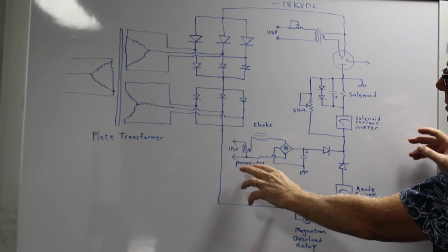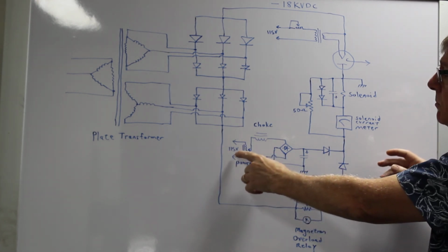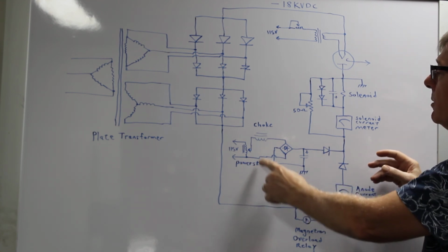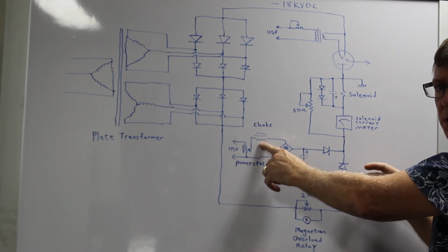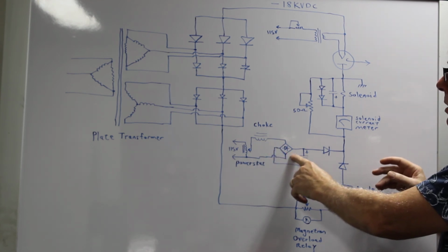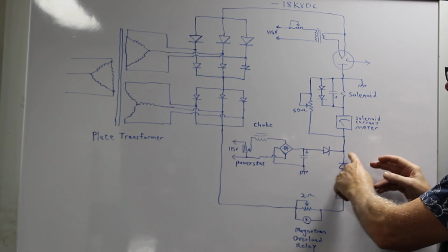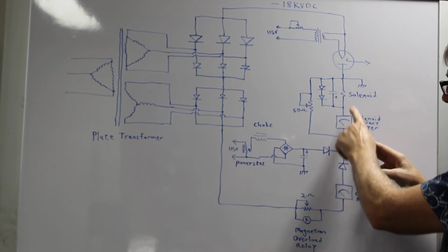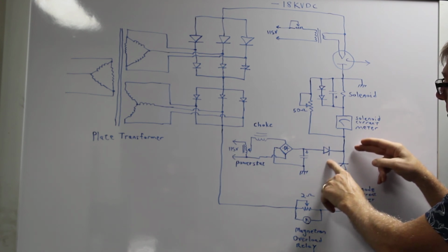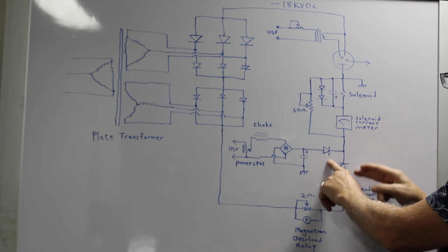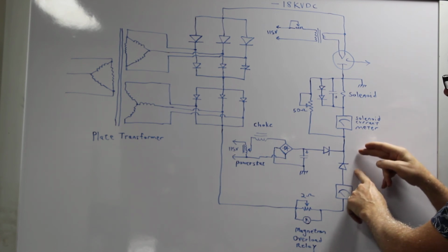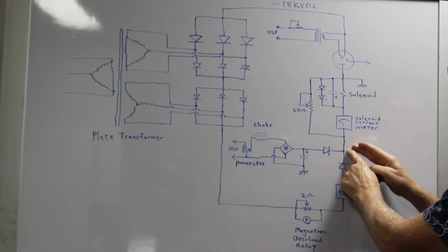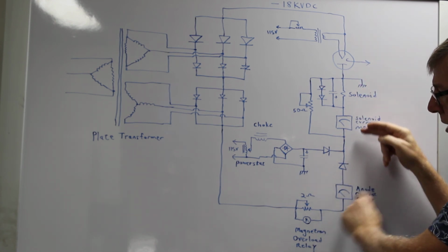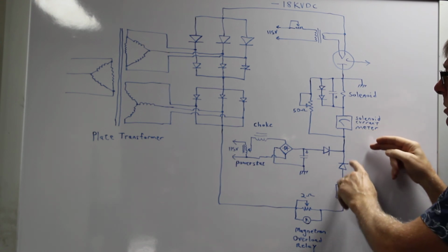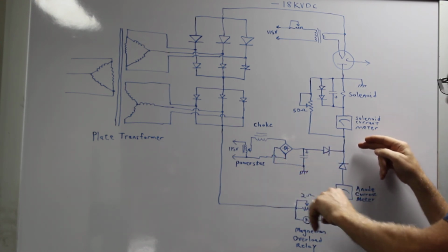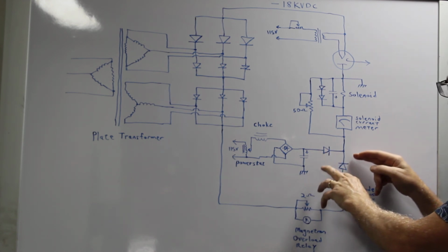So the solenoid supply is fairly simple. It's just driven by the power line through your control transformer. There's a choke here which limits the current, sort of like a ballast, and then there's a diode bridge, a filter capacitor, and then it goes into the line that feeds the solenoid here. And this diode is here to isolate the anode current, and this diode isolates as well. So the two currents can feed together and then go through the solenoid to ground, but neither of them can backfeed into the other circuit. So your anode current's not going to drive this, and that other one's not going to drive that.